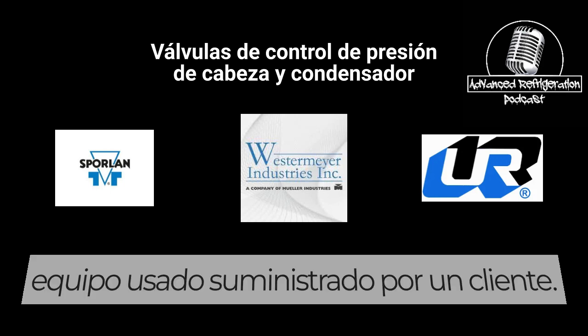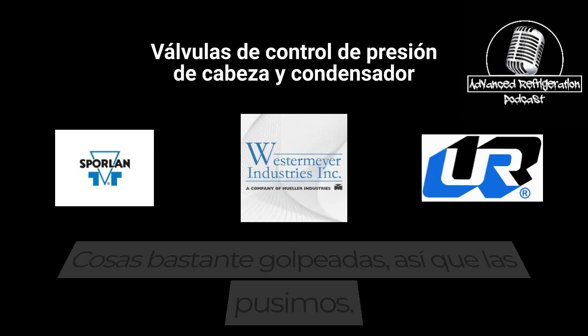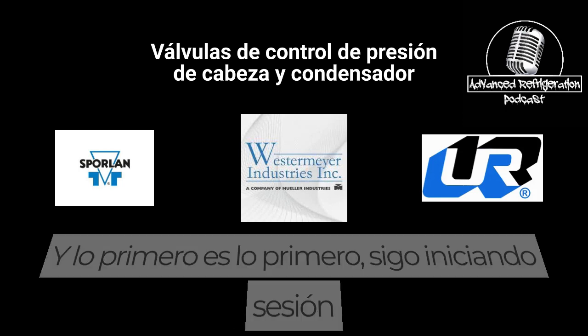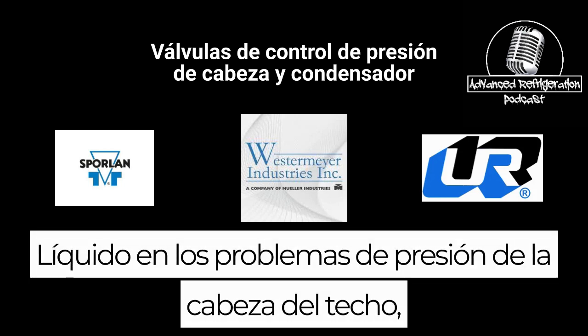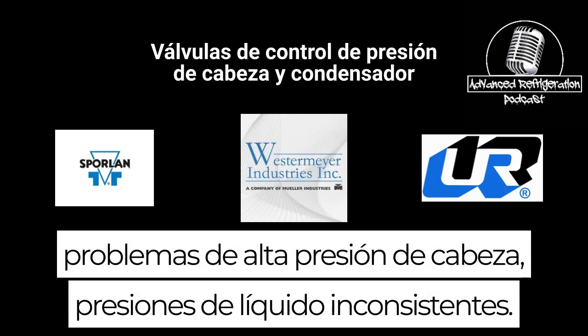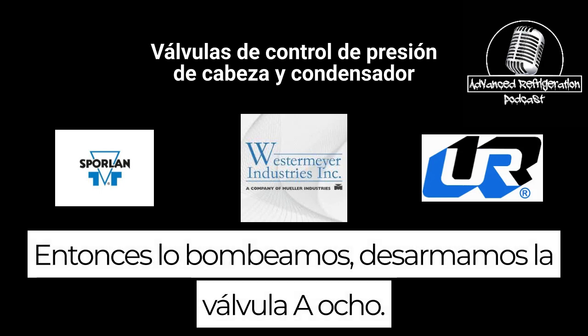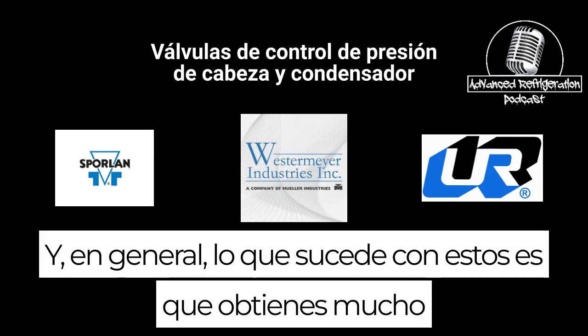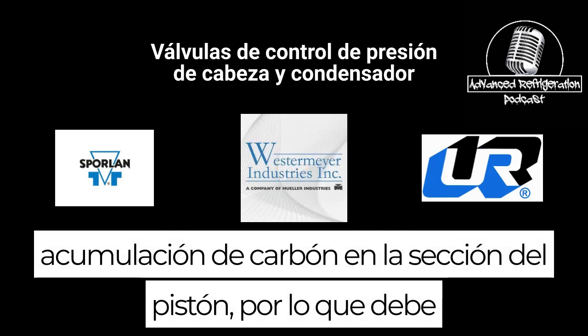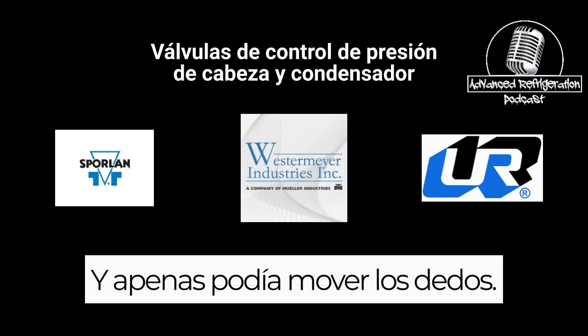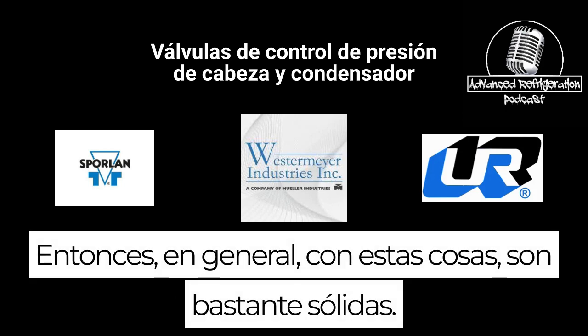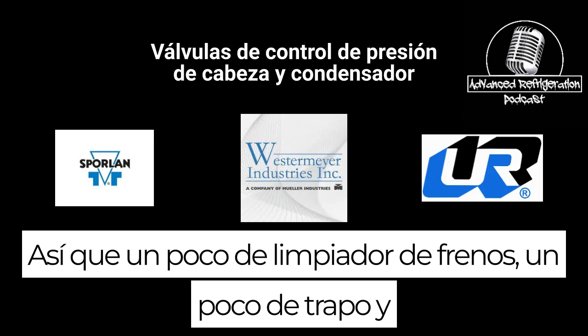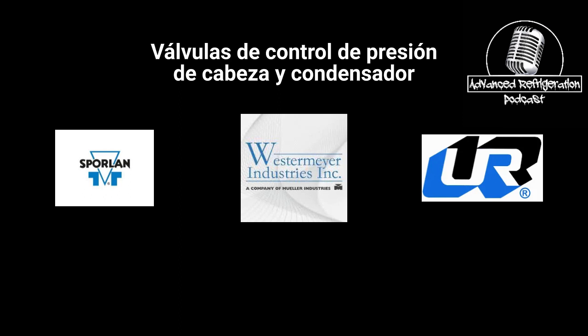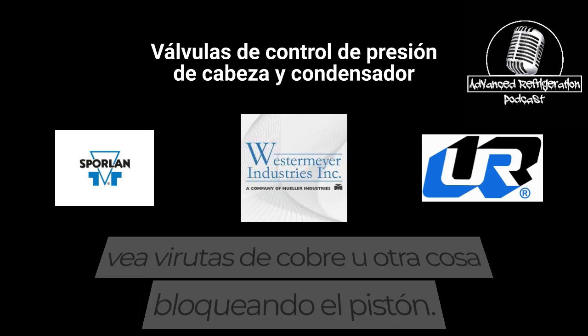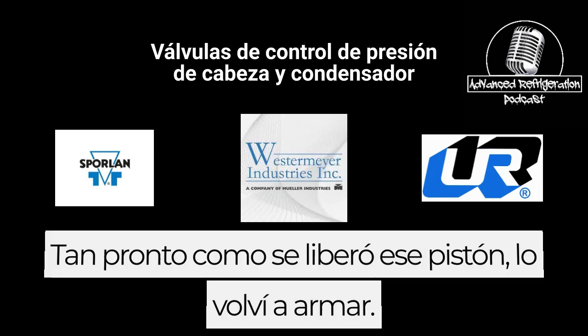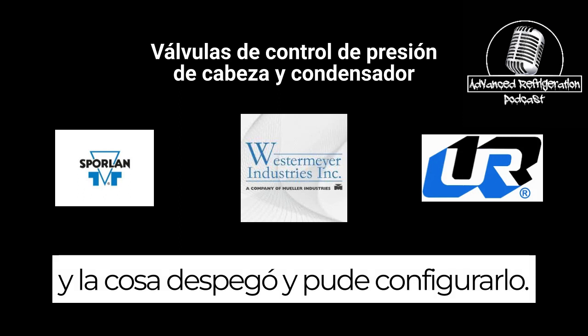We were doing a new startup on some used equipment a customer supplied. No previous history of it. Stuff's pretty beat up. So we put it in, and first things first, I keep logging liquid on the roof, head pressure issues, high head pressure issues, inconsistent liquid pressures. So we pump it down and take the A8 valve apart. Generally what happens on these is you get a lot of carbon buildup on the piston section, so you should be able to push that piston down fairly easily, and I could barely move it with my fingers. Generally with these things, they're pretty robust, so some brake cleaner, a little bit of rag and a new gasket, and this thing's ready to go. That's generally what you see in there, or you see copper shavings or something else blocking the piston. As soon as that piston was freed up, I put it back together and the thing took off and I was able to set it.